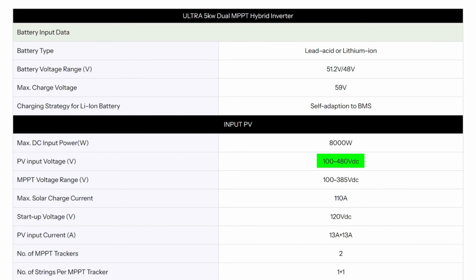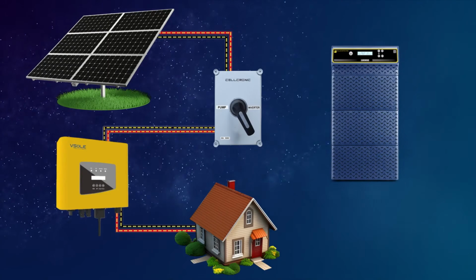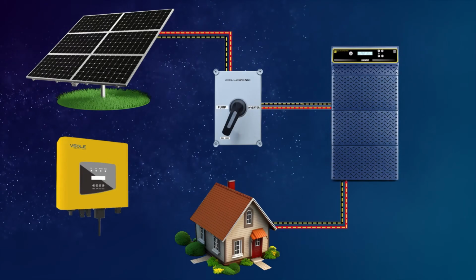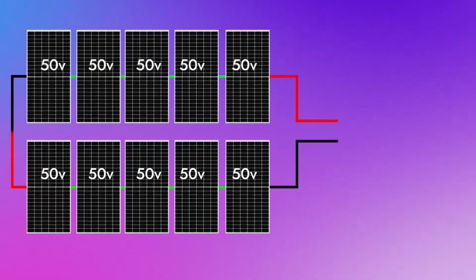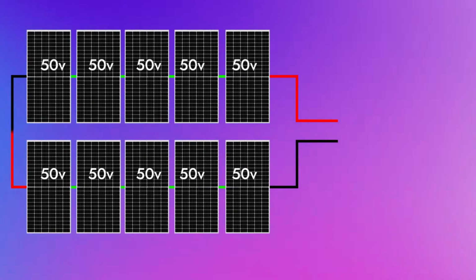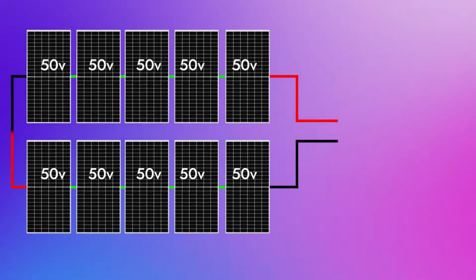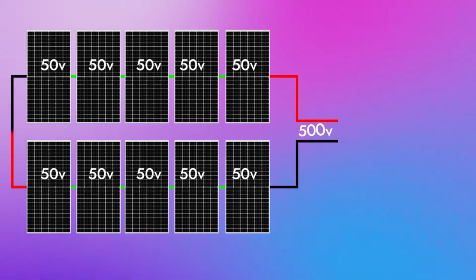This allows you to connect up to 9 solar panels in series. If you want to convert your on-grid system to off-grid as it is, you will need a DC changeover switch. With the help of this switch, you can redirect all your solar panels from the on-grid inverter to the off-grid inverter. But before choosing an inverter, you must know the VOC of your system. For example, if you have 500 watt solar panels, each panel has a VOC of around 50 volts. If you have 10 such panels connected in series, the total VOC becomes 500 volts. In the market, transformer-less inverters and inverters with higher battery banks can support such a high VOC.